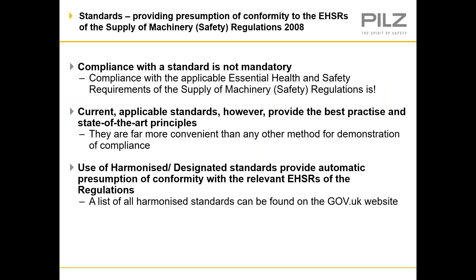Standards provide a presumption of conformity to the essential health and safety requirements of the supply of machinery safety regulations. Compliance with the standard is not mandatory — it's not law that you follow the standard — but compliance with the applicable essential health and safety requirements of the machinery safety regulations is a legal requirement. Current applicable standards provide best practice and state-of-the-art principles and are a far more convenient method of demonstrating compliance. A list of all harmonized and designated standards can be found on the gov.uk website.